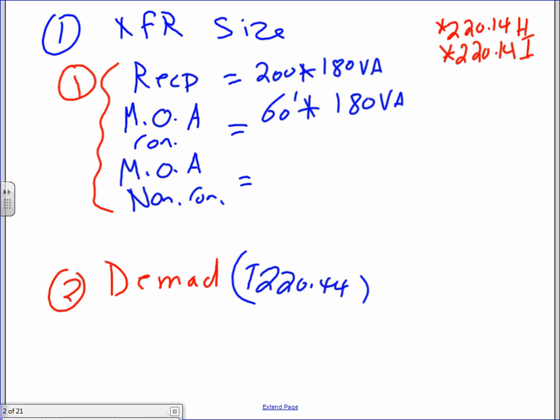The non-simultaneously used multi-outlet assembly, meaning not used at the same time, here's what we do. We take the 70, we divide it by 5, and then we multiply it by 180 volt-amps. What does that mean? For every 5 feet, do you guys remember that one from the code calculation that you did with Chad? If they're non-simultaneously used, for every 5 feet, you allocate 180. All this stuff is coming from 220.14H, I believe. Can anybody verify it? I haven't been there for a while.